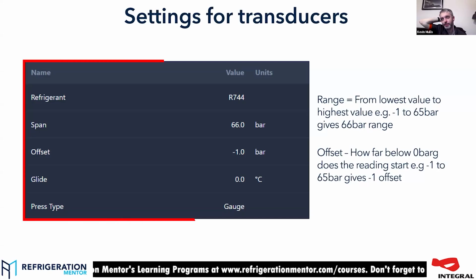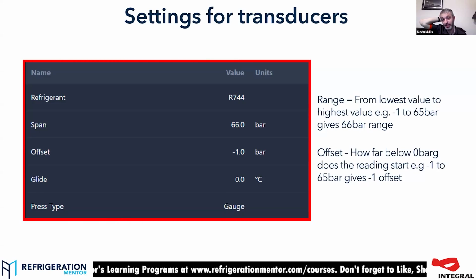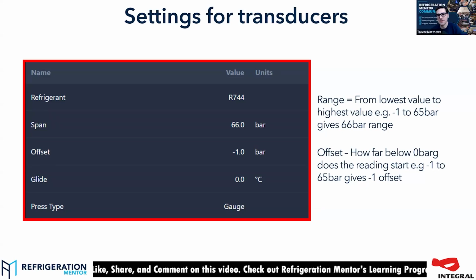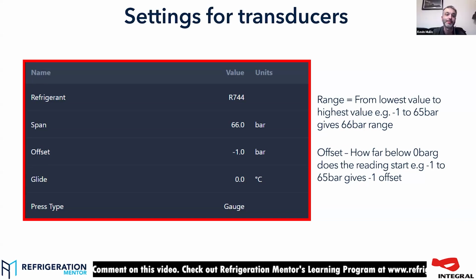I've seen a few times people put the 65 bar transducer on an LT HFC system, and you're operating at like 15 psi, 1 bar. Yeah, the transducer will read that, but the amount of current change on a 4 to 20 milliamp transducer to move it like 0.1, 0.2, 0.3 of a bar is so small, you're inviting errors into it. And 100%. It's totally just not going to be accurate for you at that range. You can't expect it to be.